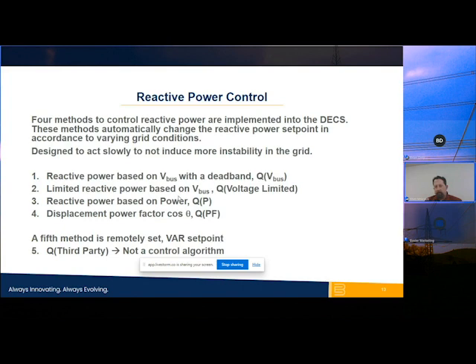Now we also have another reactive control mode called the limited reactive power based on V bus. We call that the voltage limited mode. In the voltage limit mode, what we're really doing is trying to provide a constant amount of reactive power from the machine, and we're doing that with limits. It has 4 set limits of voltage. So it will create a constant reactive power.